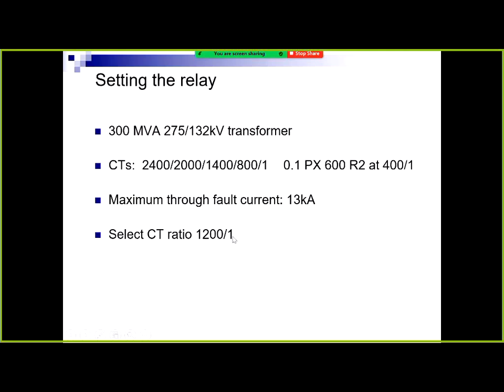So here's an example. We've got a 300 MVA transformer. The CTs are 2400, 2000, 1400, 800 to 1. That P 0.1 PX 600 R2 at 400 to 1. That's your magnetising current. The 0.1 PX stands for a protection class. There's two types, PX and P class. PX is just a bit better for transient high-speed performance, and it's what we use in our network.